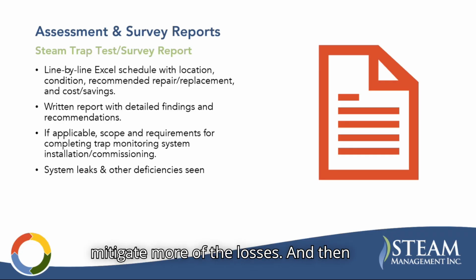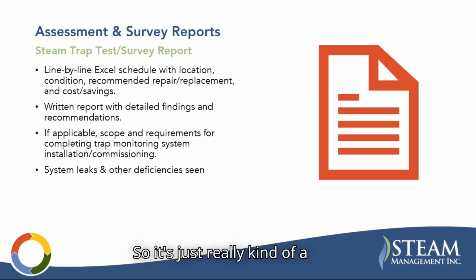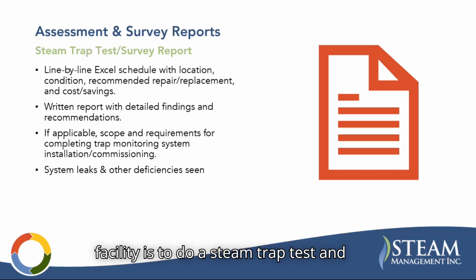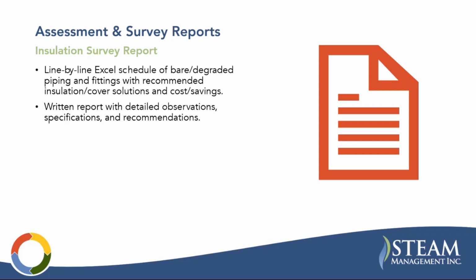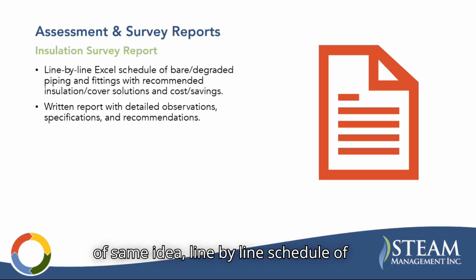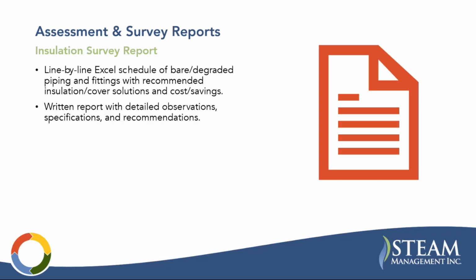And then usually through a steam trap test and survey report, we're going to see steam leaks and other deficiencies. Like I said, it is an opportunity multiplier. It's a great first step into development of scopes for a steam system. So a good approach at almost any facility is to do a steam trap test and survey. Okay, for an insulation survey report, it's the same idea: a line-by-line schedule of deficient insulation opportunities, and a written report with detailed observations.